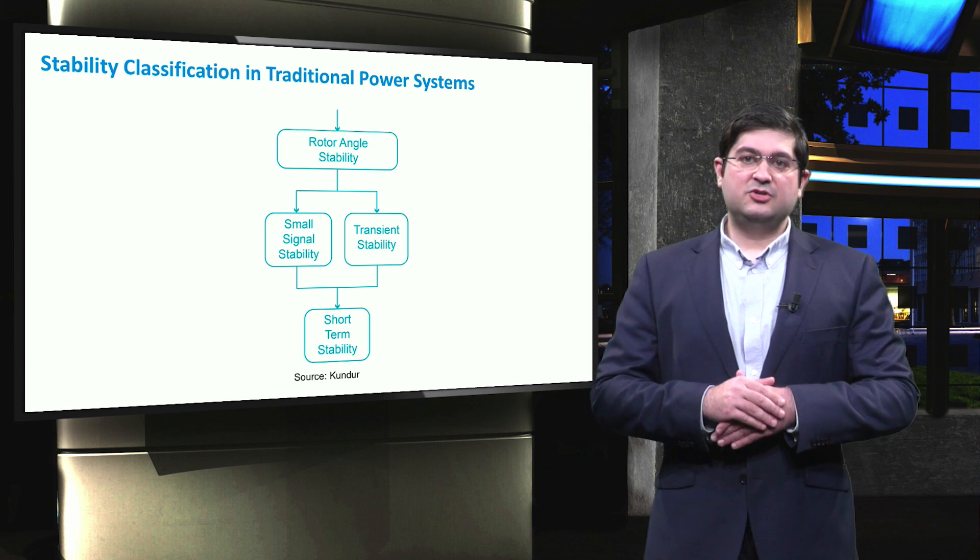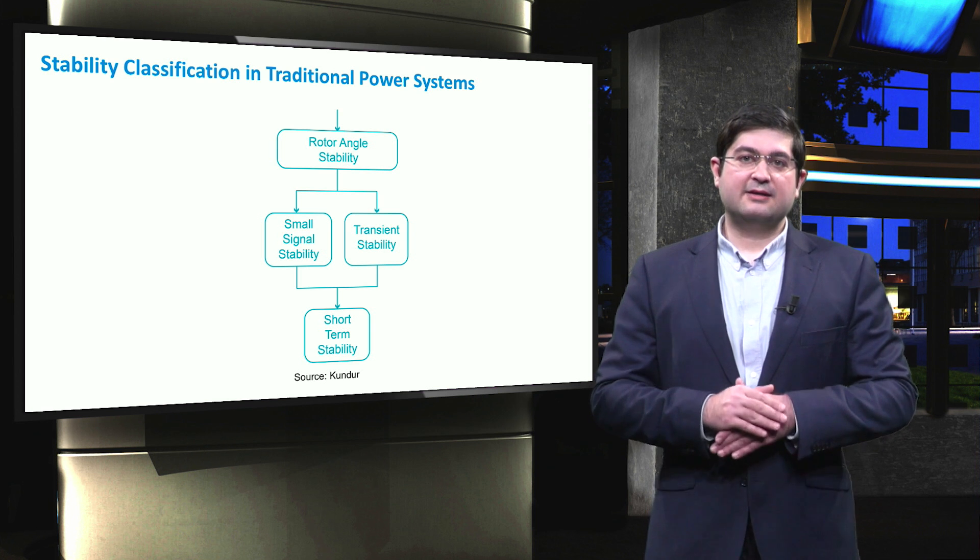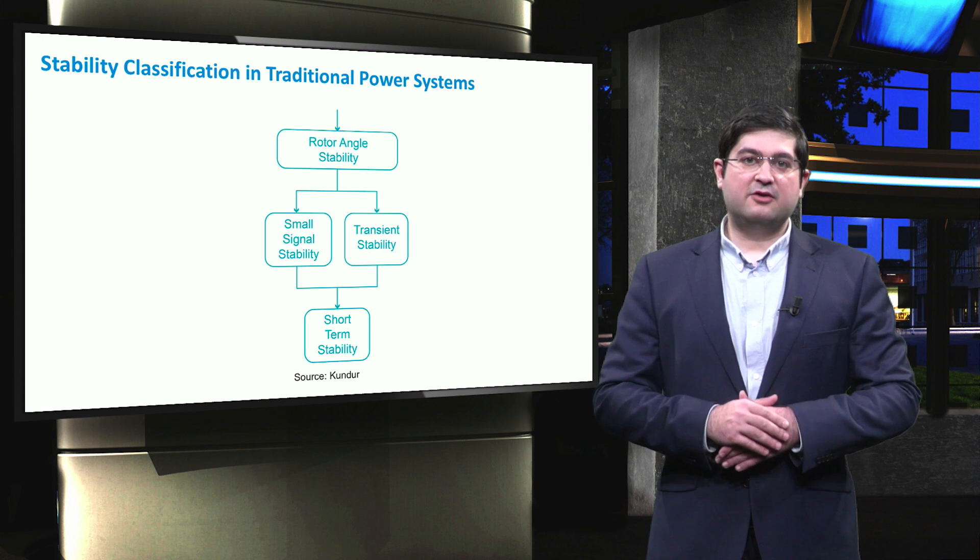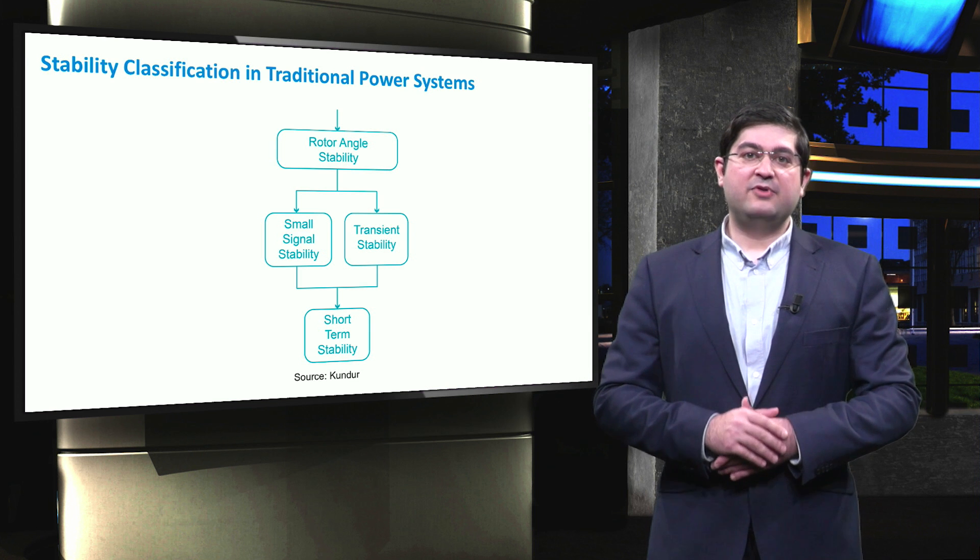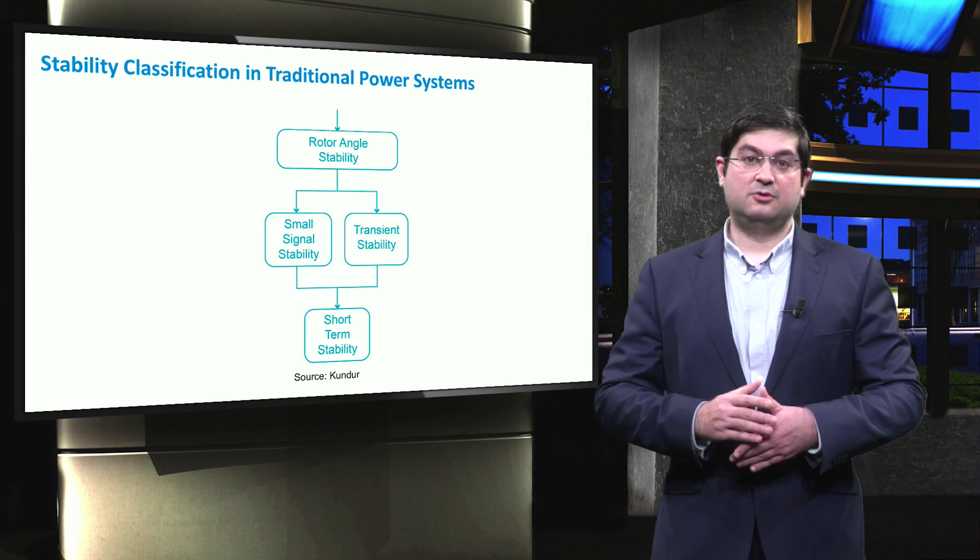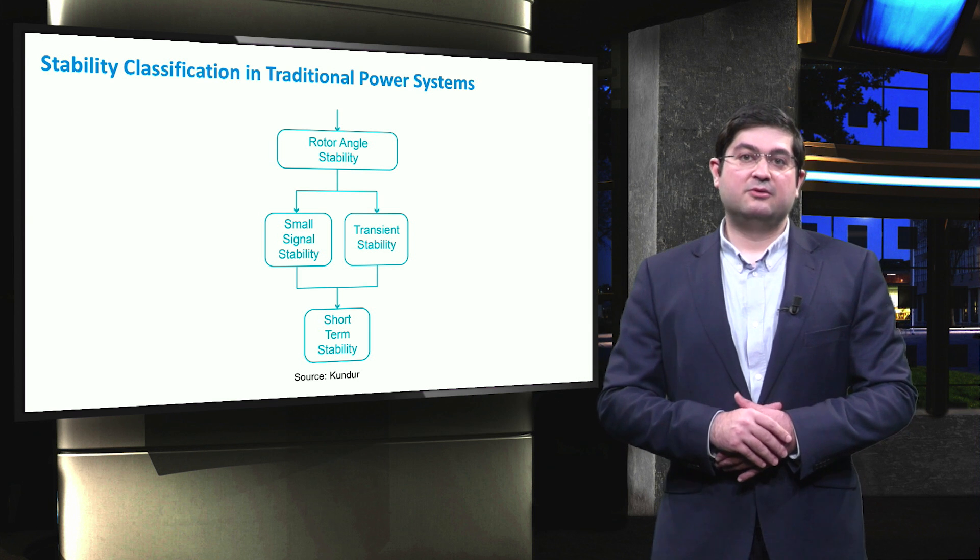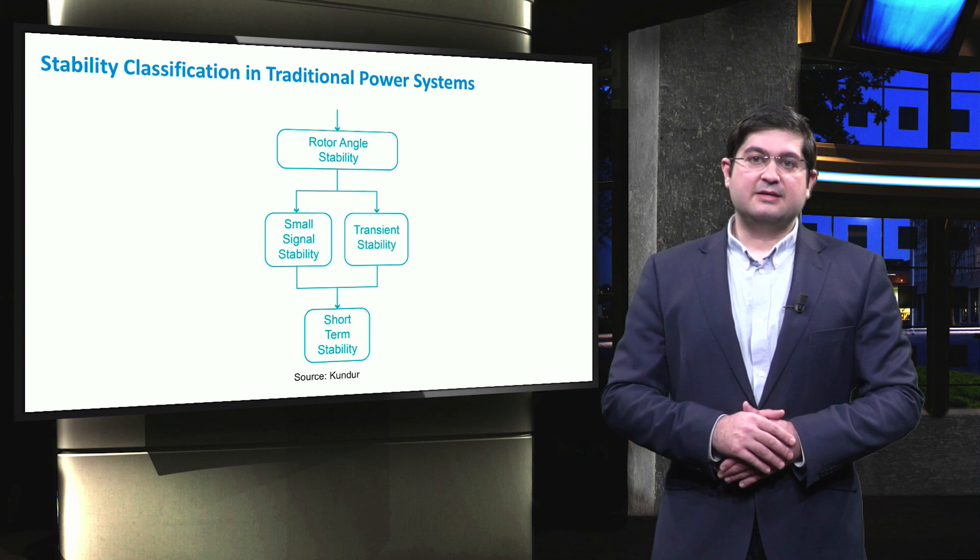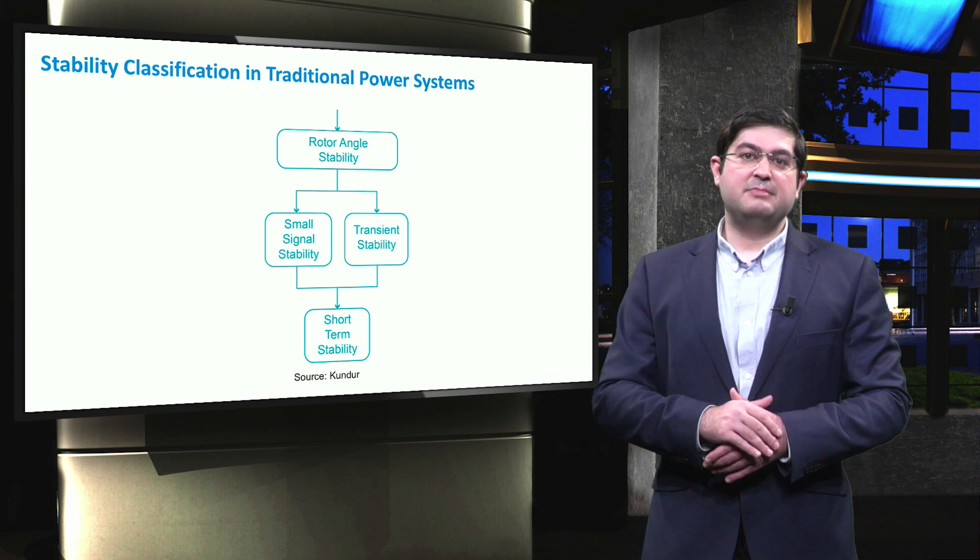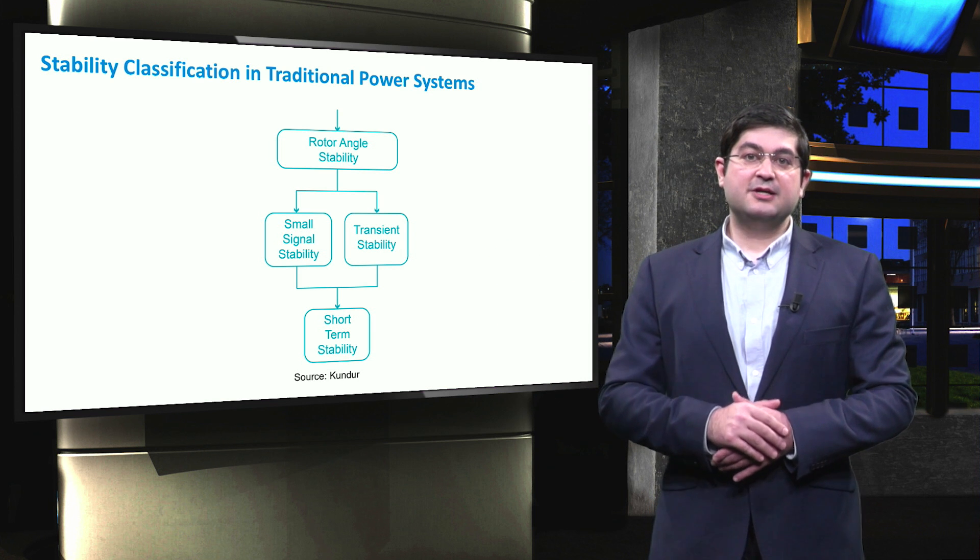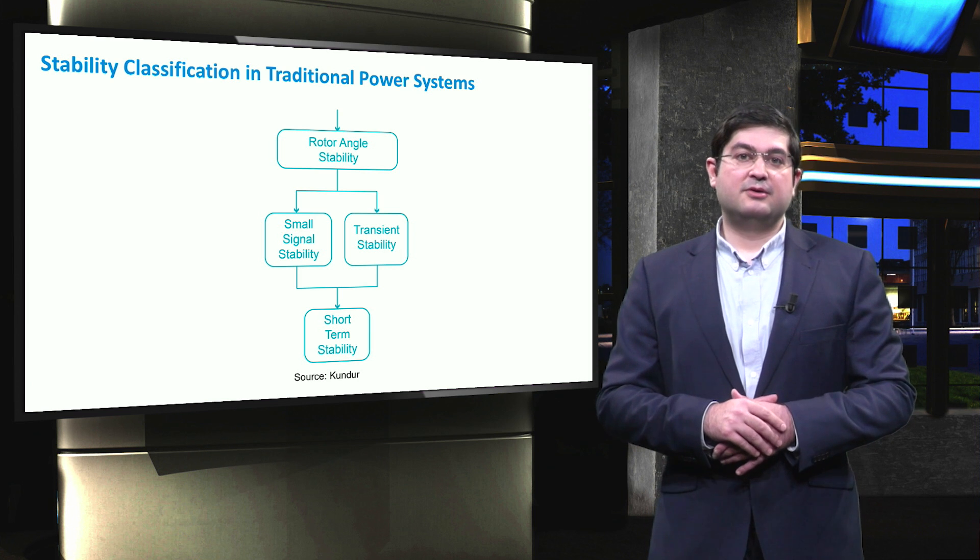In this slide, we show the first group, which is rotor angle stability. Rotor angle stability is defined as the ability of interconnected electrical grids to remain in synchronism when they are subject to disturbances or faults, for instance, single phase or three-phase to ground faults. Rotor angle stability is the shortest stability phenomena for about few hundreds of milliseconds, which in general is divided into either a small signal stability or transient stability.